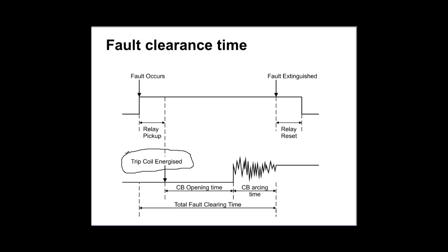So when you say the total fault clearance time, it is a combination of the relay operation plus the circuit breaker operation. Correct. And don't forget, the relay should be reset again, ready for the next operation. So that's how it is. That's where we can say now the system is clear, safe, and you can go and do operations. Yes, this is what I mean by that.